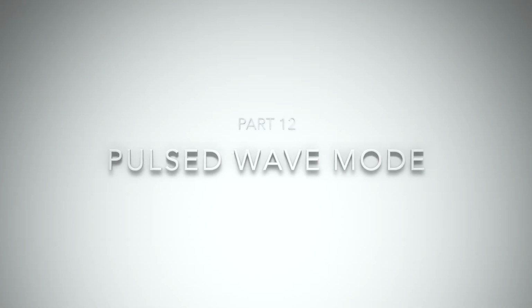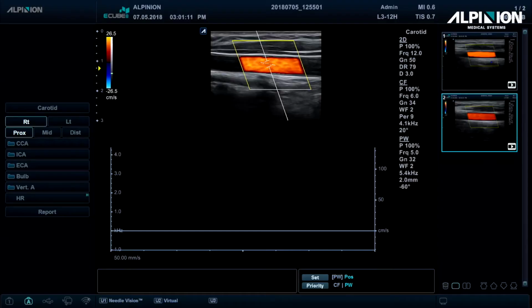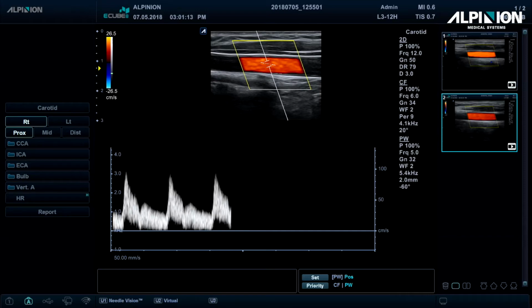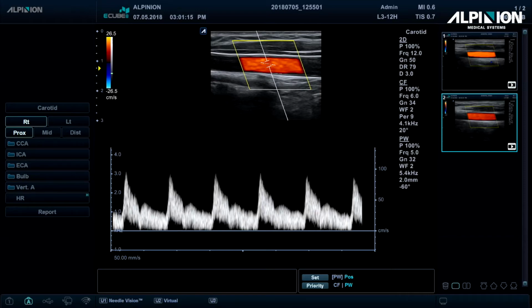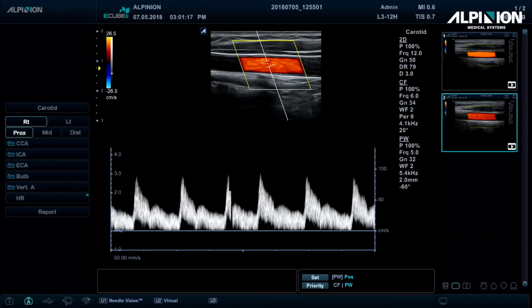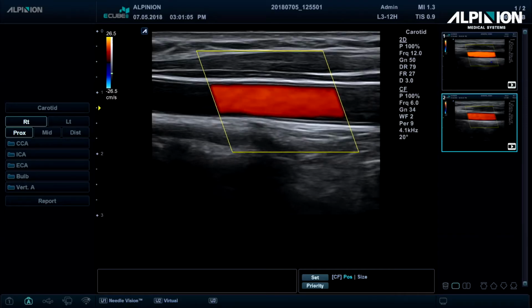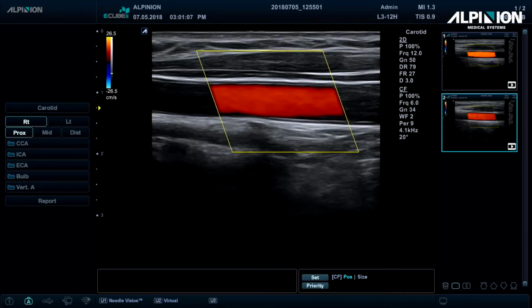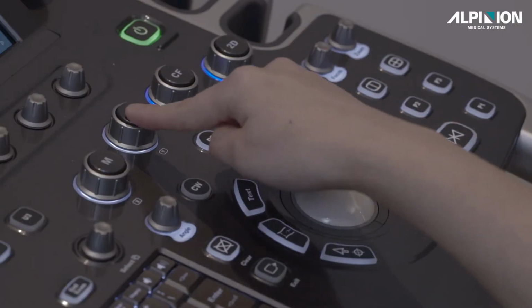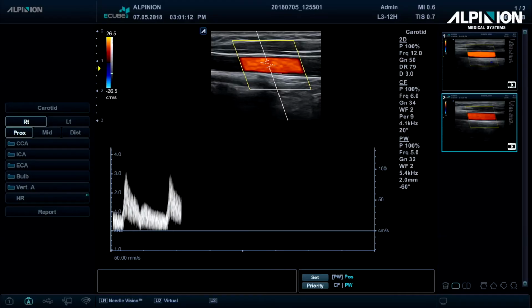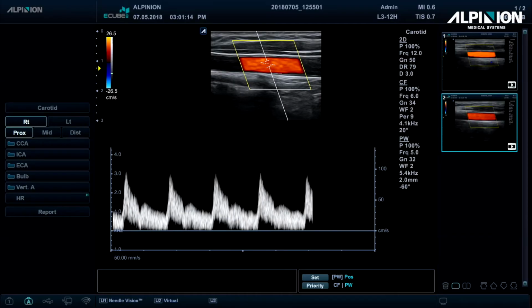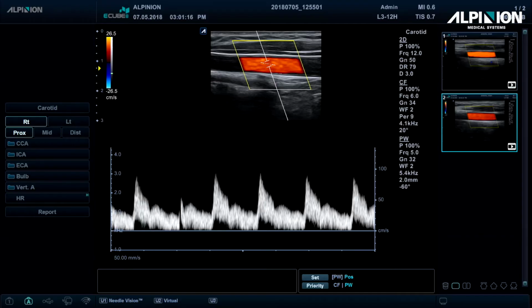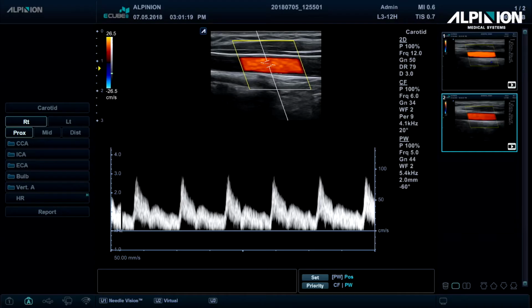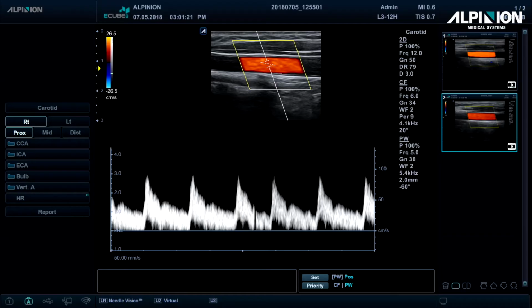Part 12. Pulsed Wave Mode. Pulsed wave Doppler allows us to accurately measure the velocity of blood in a precise location and in real time. Once you acquire the proper vascular image in the color mode, press PW button to activate the pulsed wave mode. PW spectral gain is also adjusted by using the PW rotary key.